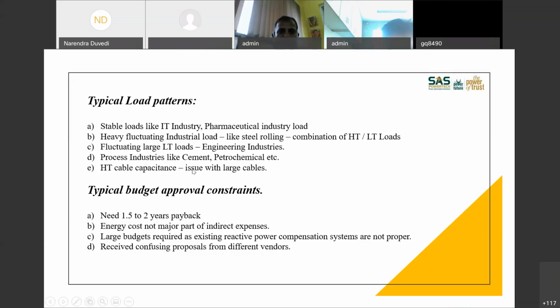HT cable capacitance. We were not considering this earlier because HT cable capacitance used to overcompensate your reactive power consumption, so you were not getting any penalty for it. But now it is likely that you will get a penalty because of this. I'll explain what it is in the next slide.